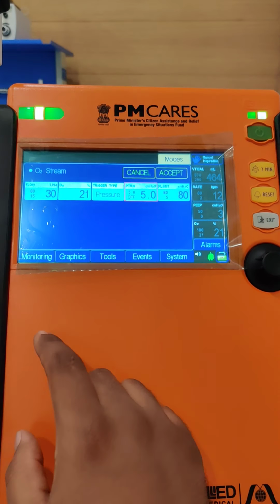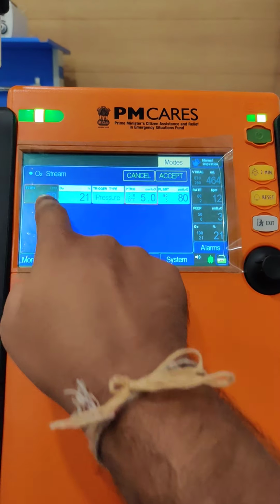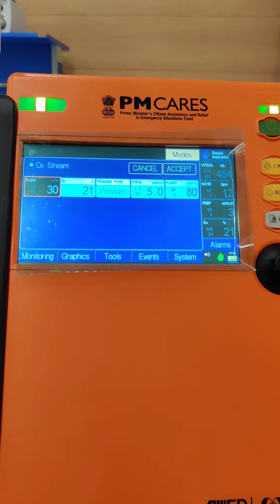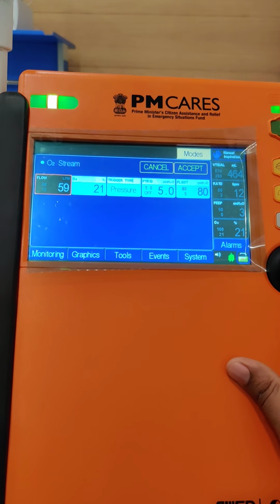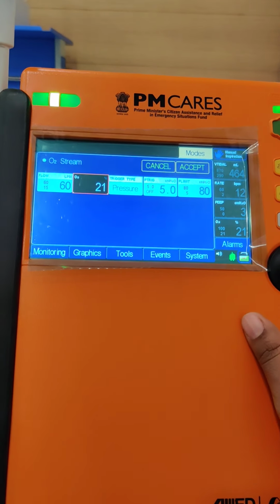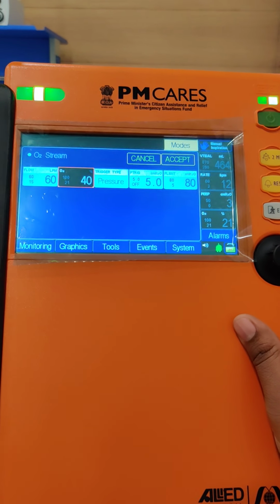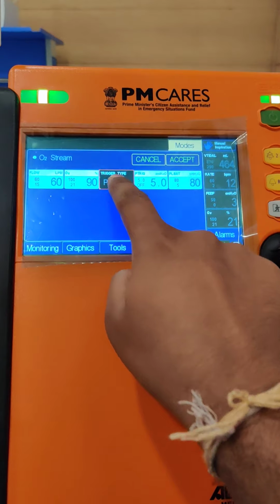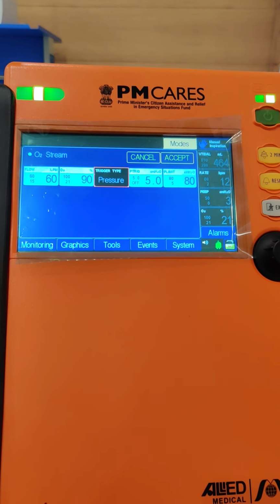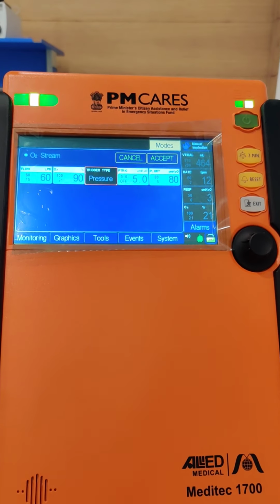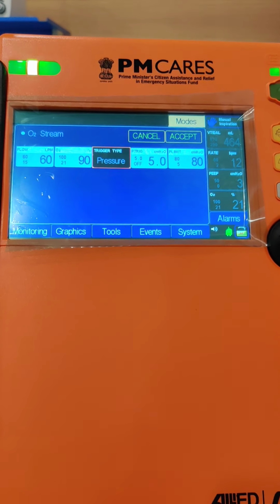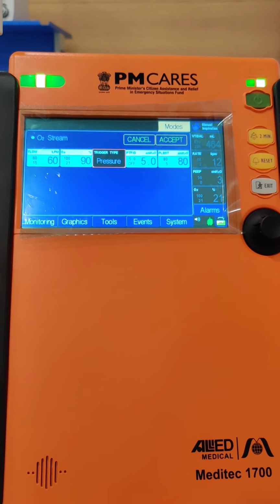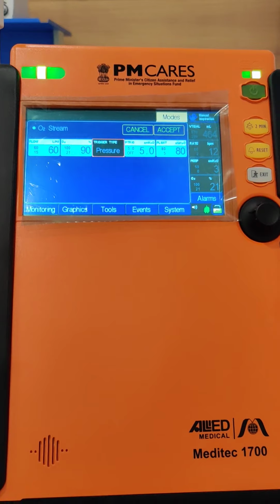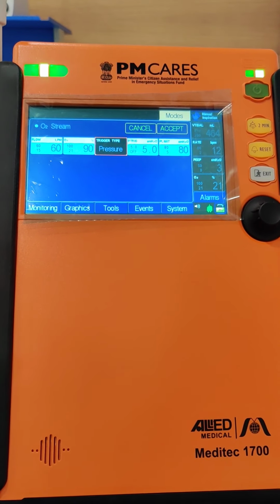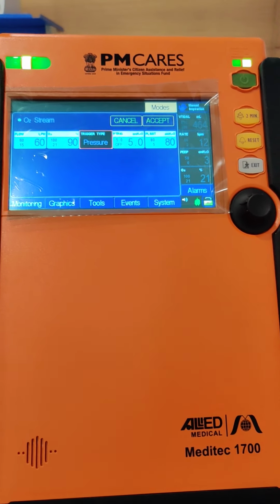So in this mode of ventilation you can deliver a flow of up to 60 liters per minute to the patient, and you can set the oxygen from 21 to 100%, and these are the triggers. So on these values the patient will be getting a continuous flow of 60 liters per minute at 90% oxygen, and you can give high flow nasal cannula therapy to the patient with the help of this mode.